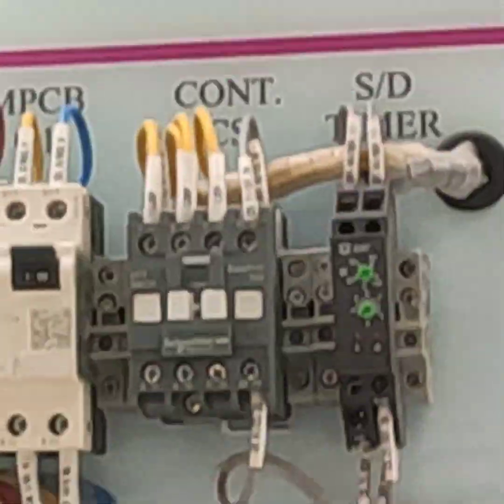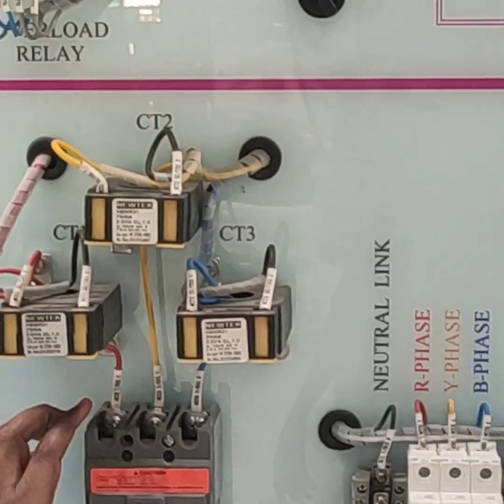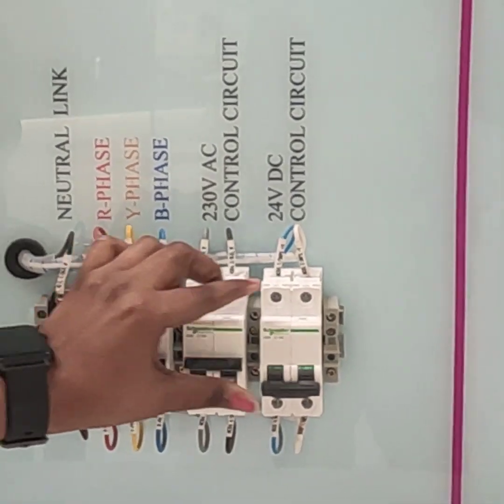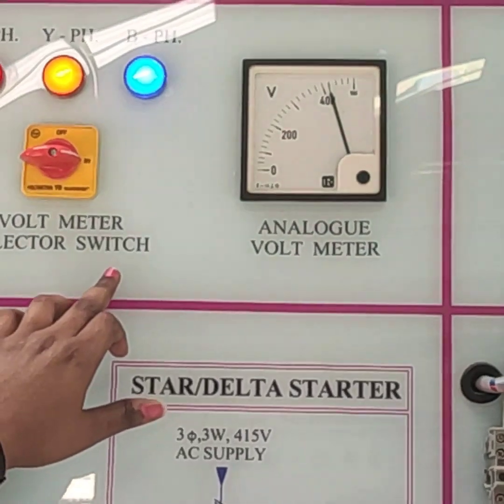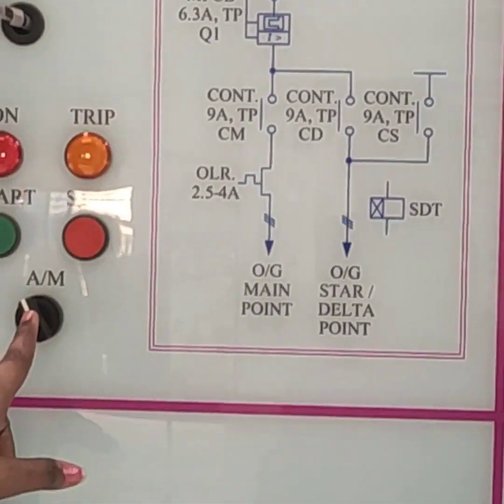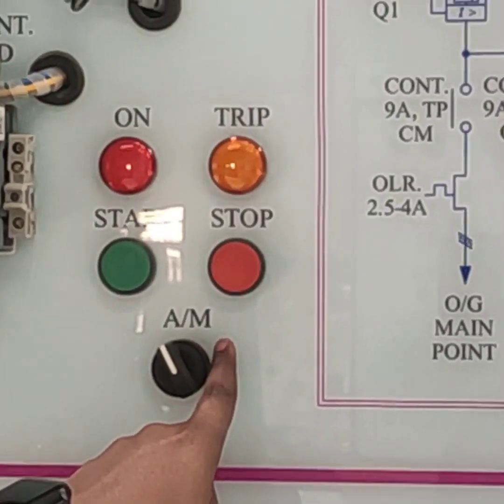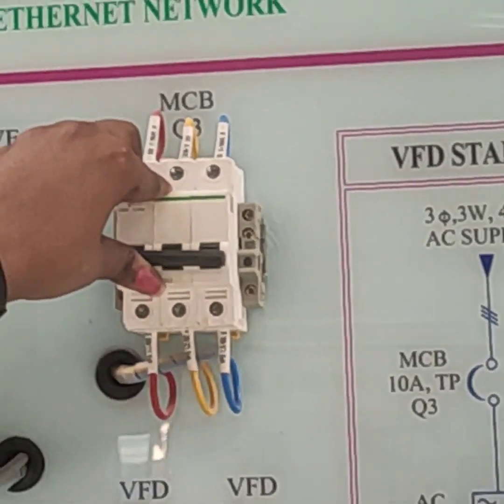Come to here, switch on the main supply and come to the simulator. Switch on first MCB Q1, switch on the main incomer line, and switch on all these MCB miniature circuit breakers. Check the position of the voltmeter selector switch — select RY mode. Here we can adjust it for automatic mode or manual mode. Next, switch on MCB Q3.